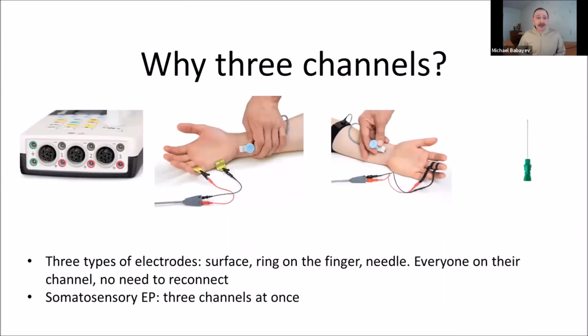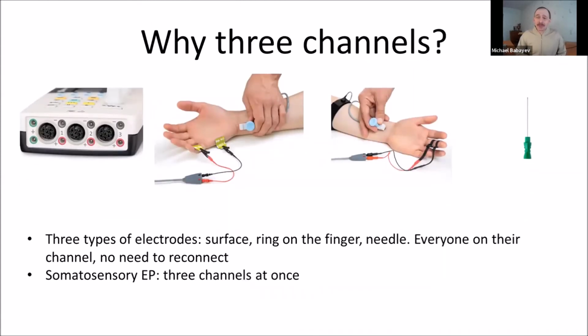You can ask us, for example, why 3 channels for an EMG machine? There are a few reasons for it. First of them, there are 3 types of different electrodes that each doctor uses. The first type is surface electrodes for motor conduction velocity, for example. Another type is rings on the finger for sensory conduction velocities. And the third is the needle electrode. All these types of electrodes have their own cables.